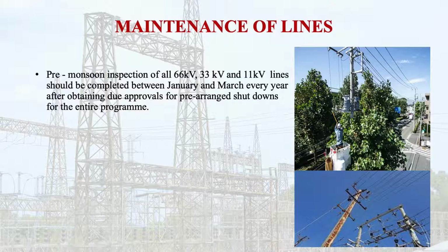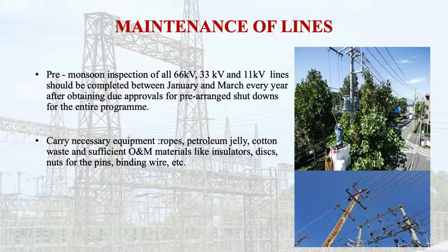Let us begin this session with the maintenance of line. Pre-monsoon inspection of all the 66 kV, 33 kV and 11 kV lines should be completed between January and March every year after obtaining due approvals for pre-arranged shutdowns for the entire program. The staff responsible for the pre-monsoon inspection should carry all the necessary equipment such as ropes, petroleum jelly, cotton waste, and sufficient O&M materials like insulators, disc, nuts for the pins, binding wire.